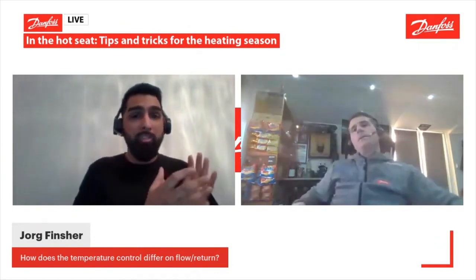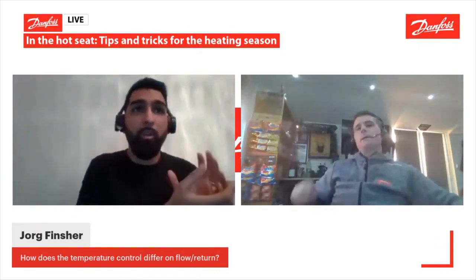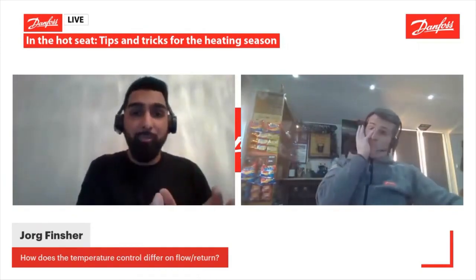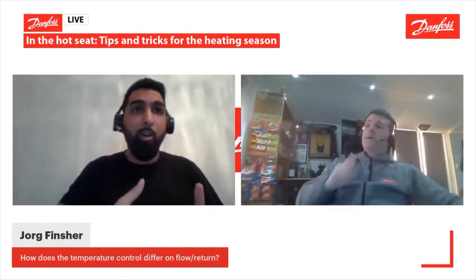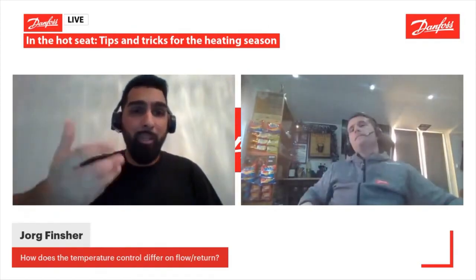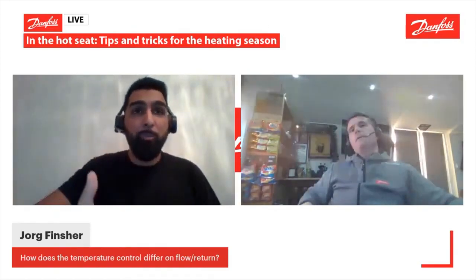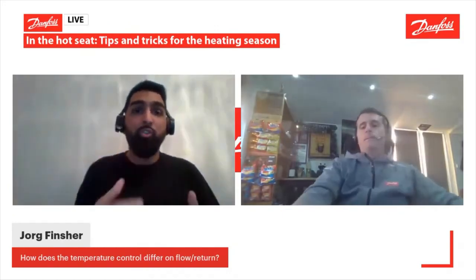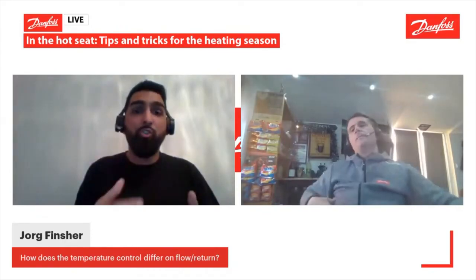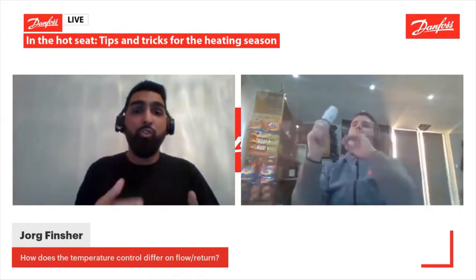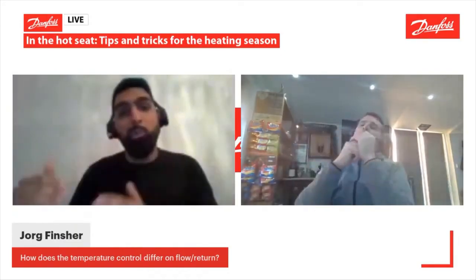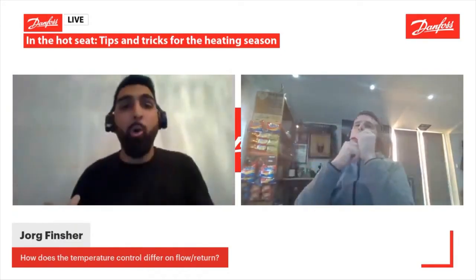What happens is when that temperature of water reaches the radiators, which is your heating emitter, a lot of the heat should be dissipating. A lot of heat should be being released from the radiators. Okay, so when it's being released from the radiators, what we're actually trying to do is release approximately 20 degrees Celsius of that heat out into the atmosphere. So our return is 20 degrees Celsius lower.